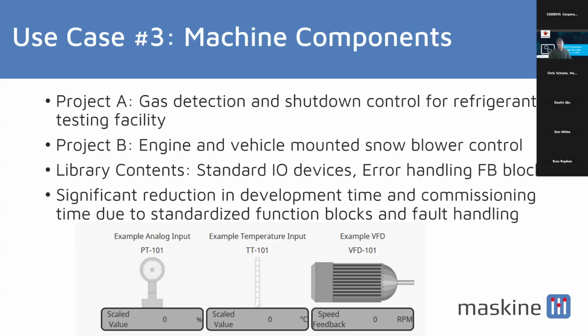These systems aren't the largest, maybe 100 points of I/O combined, but when you get into 500 plus I/O devices it really adds up. In both projects the same library was used, and the logic handling was consistent, allowing rapid development through code reuse and standardization. No copy and paste needed, it's just good to go.